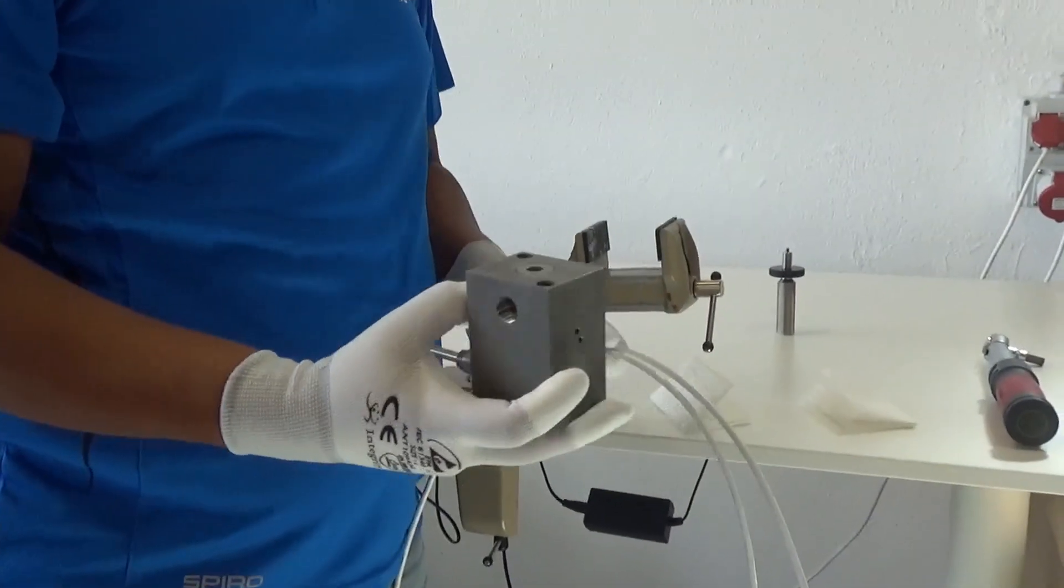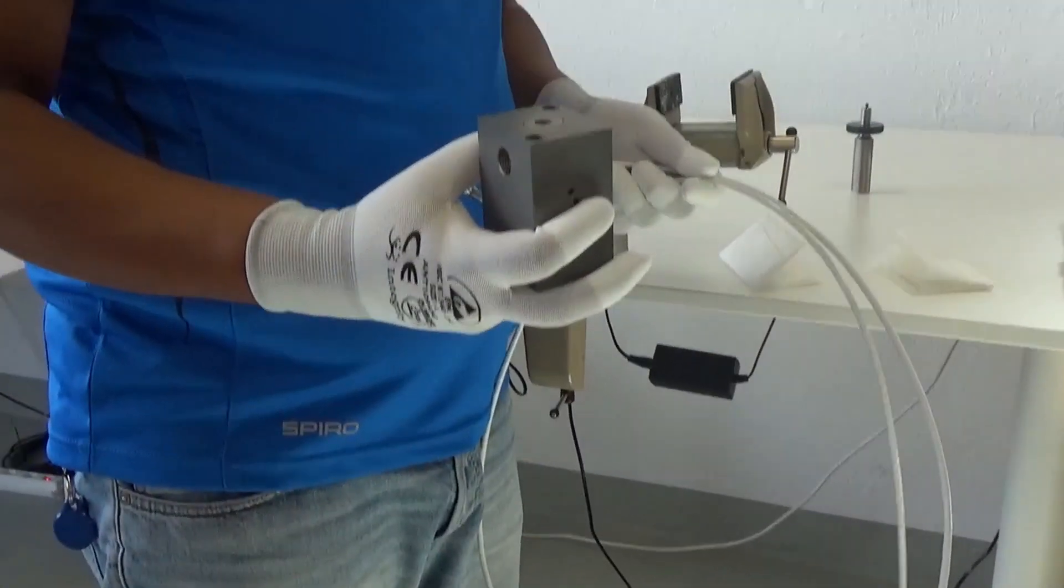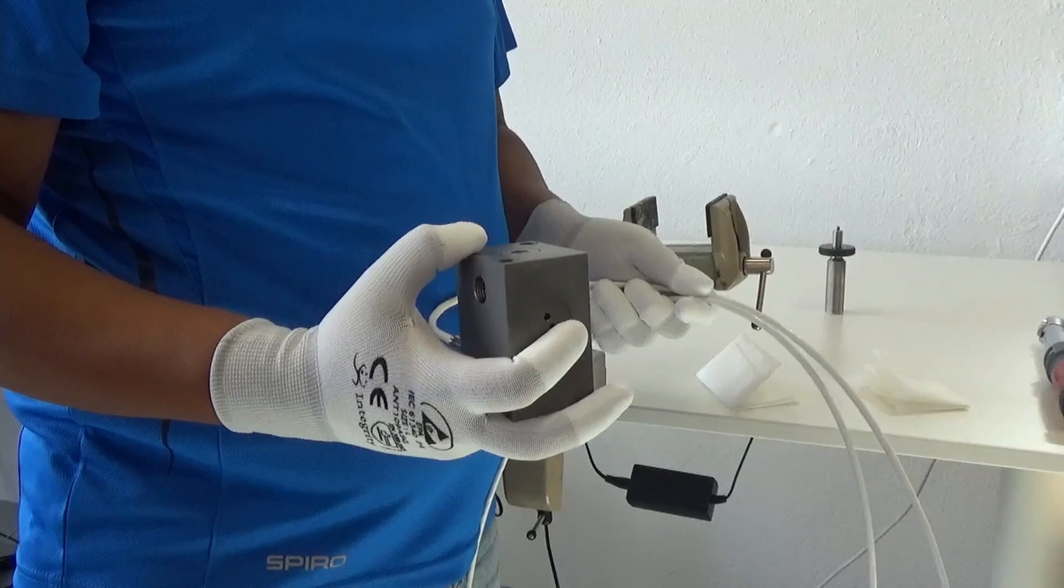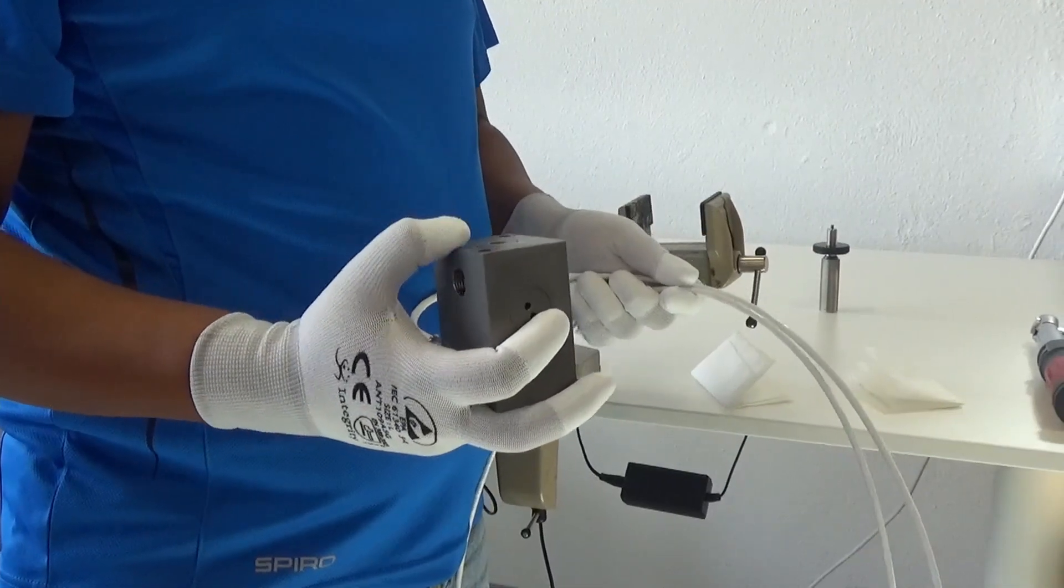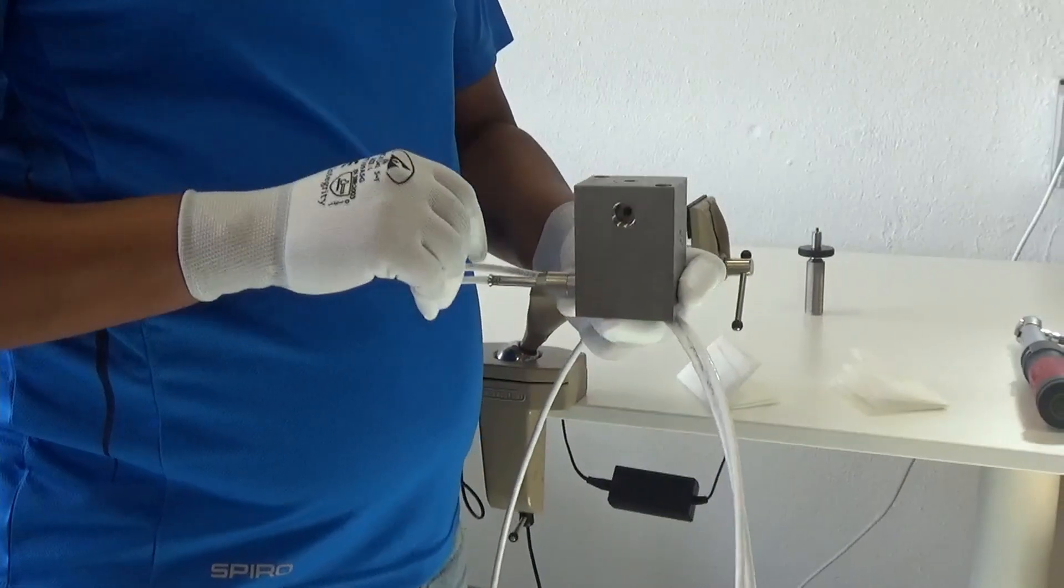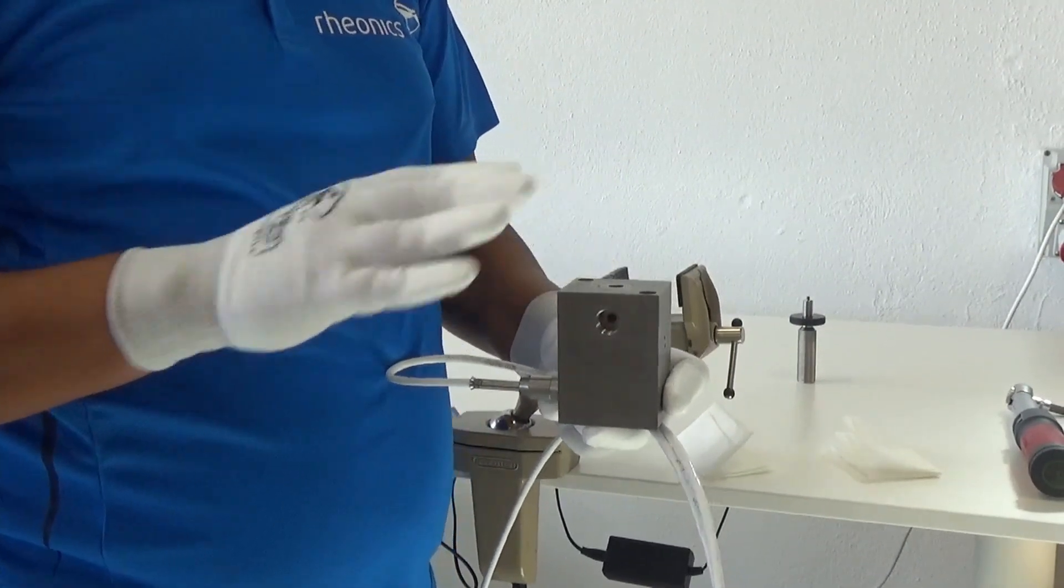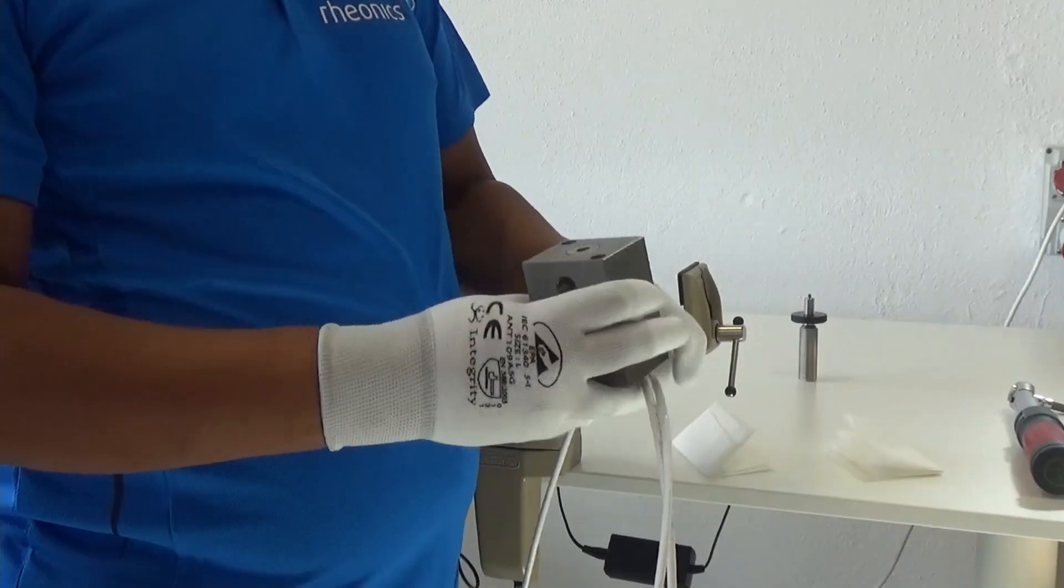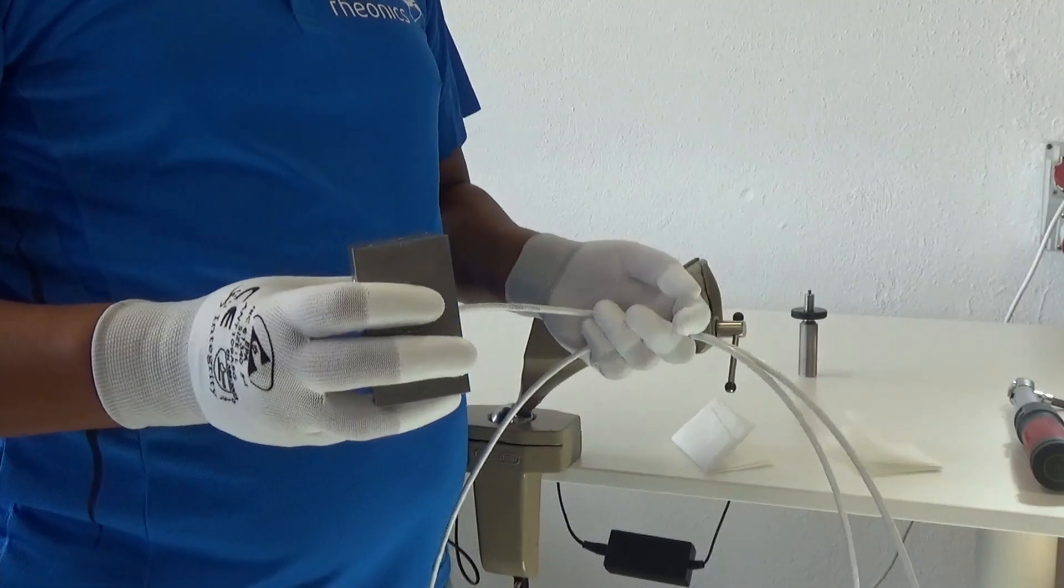Today we are going to talk about the Rheonics DVM, the high pressure, high temperature density and viscosity sensor. This monitors density, viscosity and temperature of your sample at the same time. Pressure wise it's rated up to 2000 bar which is 30,000 psi and temperature wise it's rated up 200 degrees centigrade which is about 450 degrees Fahrenheit.